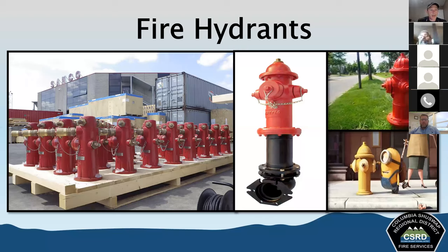Hydrants located on dead end water mains, like I had mentioned before, without the circulation of the water, you tend to have situations where water pressure can drop unexpectedly. Closed isolation valves that we weren't aware of, possibly restricted mains. Over time, the water mains become restricted with sediment and other kinds of debris, mineral deposits, and that can end up impeding the flow of water through these mains. And pipes or hydrants that end up being frozen, and that's something we run into as well.